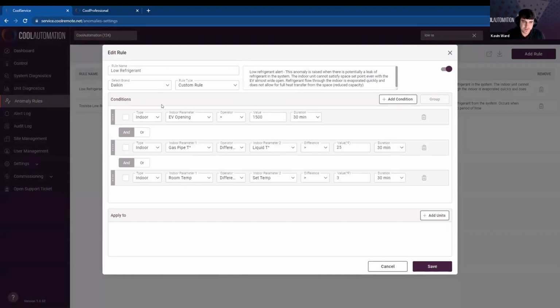So our system now with this custom anomaly will actively monitor each of your indoor units for the valve position, the room temp and the set point being satisfied, and the delta between the gas and liquid temperatures. So how quickly is that refrigerant evaporating through that coil? If the room temp is not satisfied and the valve is wide open, this at least indicates a possible case of low refrigerant. And let's see how this looks when it's triggered at this site.